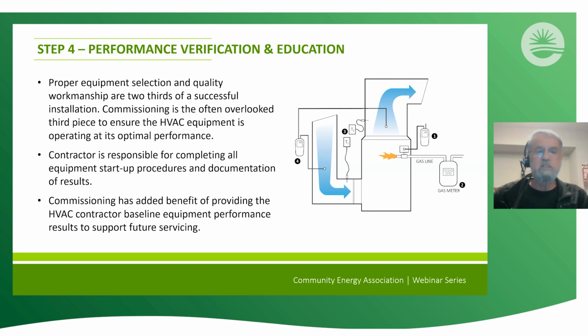Performance verification and education. Proper equipment selection and quality workmanship are two thirds of a three-act play, and you've got to have that final act to resolve everything. That final act is commissioning. It's often overlooked, as an understatement. We have the hardest time with it. We design systems all the time where it's very clear, it's even in the contract, that it's the contractor's job to do the commissioning. It is assumed by the manufacturers and the suppliers that the contractors will do the commissioning. It's assumed by warranty providers that the contractors will do the commissioning. The only place where it's not assumed is in the arena of contractors themselves. Now, I'm generalizing, of course, there's a lot of good contractors that do this, fortunately, but they're a minority.